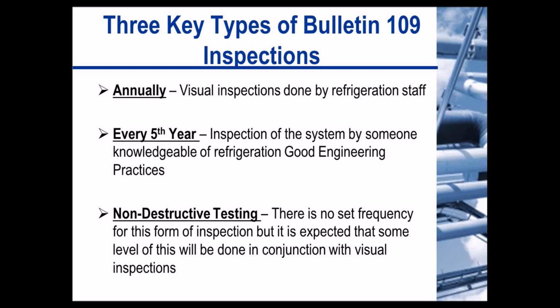Every 5th year, inspection of the system should be done by someone knowledgeable of refrigeration and good engineering practices. Now, non-destructive testing, there is no set frequency for this type of testing. But it's something that often comes up from observations or from assessments that are made during either of these two other inspections.